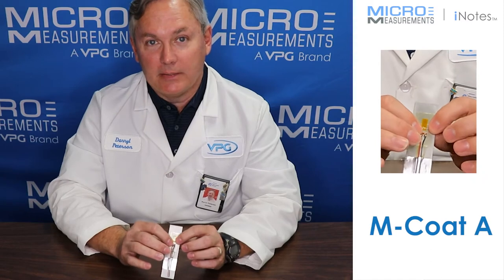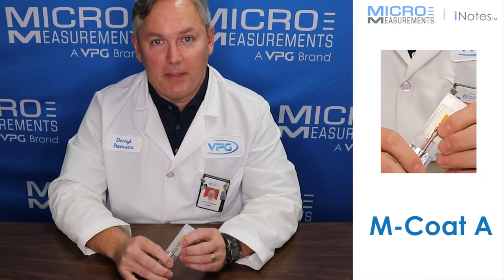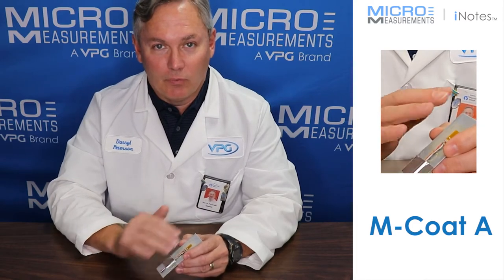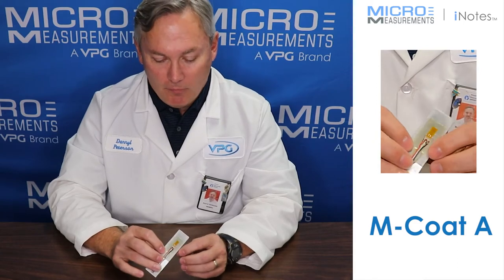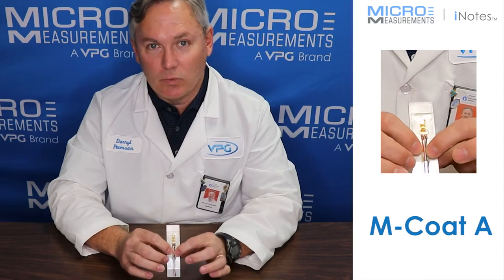The nice thing about M-Coat A is that it's very easy to put on. It comes in a bottle with a brush cap applicator. You just brush it on over top of the strain gauges, going around the gauge and extending it beyond the flow out of the adhesive. It forms a thin hard layer over top of the strain gauge and helps to hold down your lead wires as well.